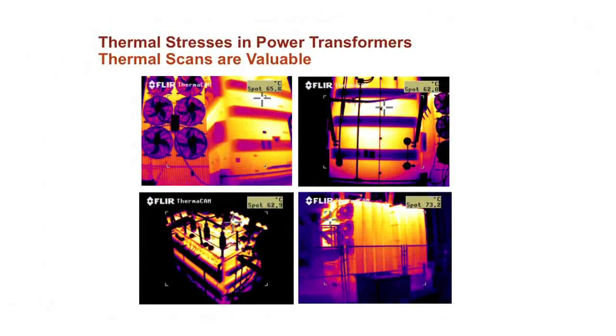Also with thermography, you can see if there are problems with the cooling. Here, you can see this cooling is red, and this one should be too, but it's not, because for some reason it's blocked or it's been shut off. Often you can also see if there are hot spots around the tank. So this can be a very good tool for seeing if there are any issues with the transformer.